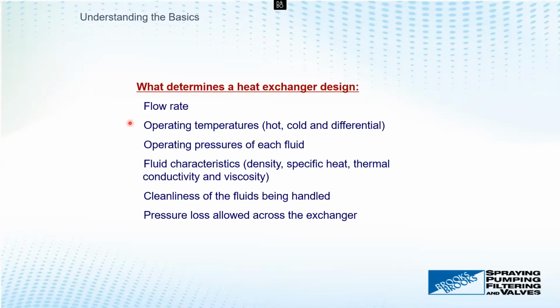We need to know the pressure or the temperature differential as well. Of course, we've got to know the pressures, the flows, all that good stuff that's going on there. And then to be most efficient, choosing between a shell and tube or the plate and frame style, we want to know the densities, the specific heats, the viscosities, those kinds of things. Those all will tell us if we're able to use a plate and frame, because remember, a plate and frame is the most efficient heat exchange technology that there is.